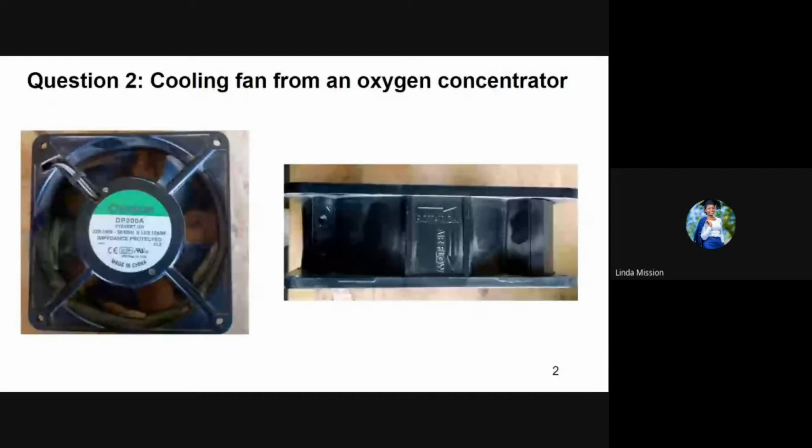Another thing you must consider when installing the cooling fans in your concentrators is the orientation of the fans. The cooling fans used in oxygen concentrators have 2 arrows labeled on them. One arrow shows the direction of rotation of the fan propellers, and the other arrow is there to show the direction of airflow. In some concentrators, such as the DeVilbiss 525, the cooling fan is there to pull hot air from the concentrator into the surrounding environment. So the arrow for the airflow on the fan for the DeVilbiss 525 points away from the compressor.